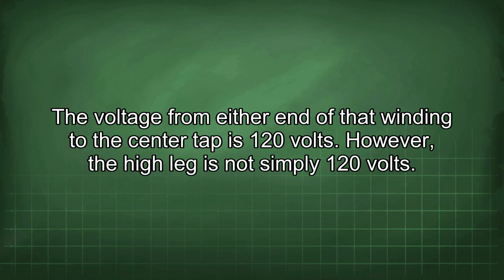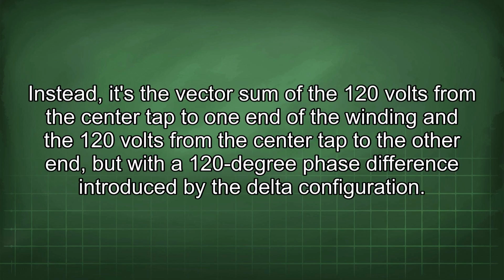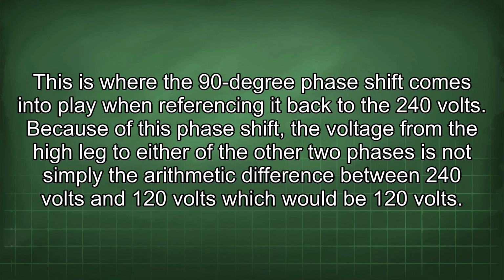However, a high leg is not simply 120 volts. Instead, it's the vector sum of the 120 volts from the center tap to one end of the winding and the 120 volts from the center tap to the other end, but with a 120-degree phase difference introduced by the delta configuration. This is where the 90-degree phase shift comes into play when referencing it back to the 240 volts.